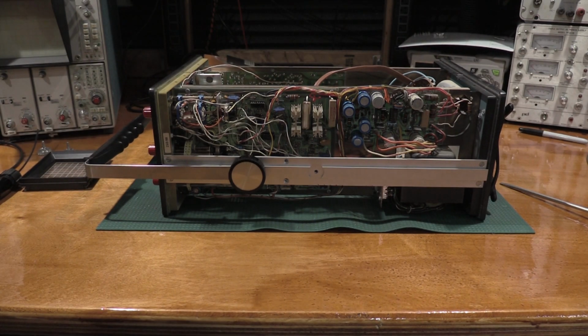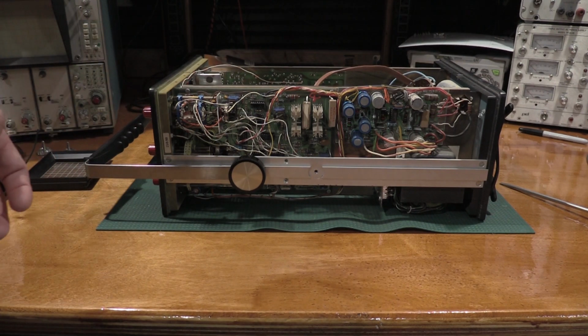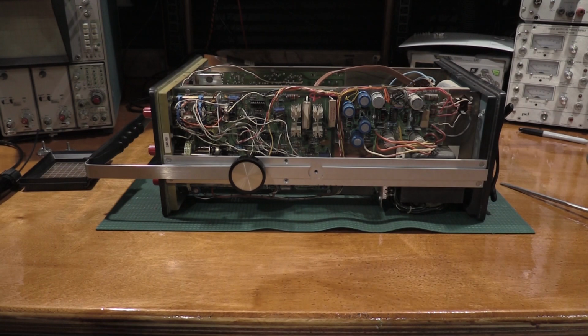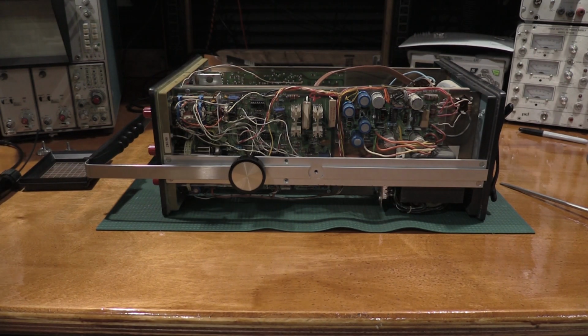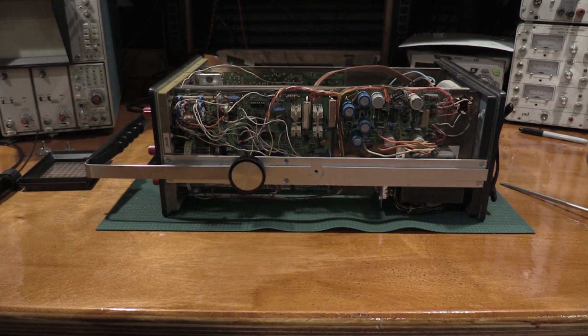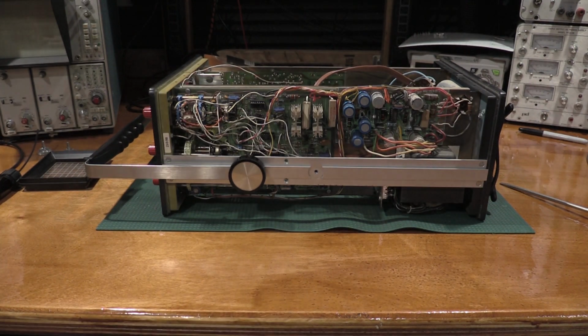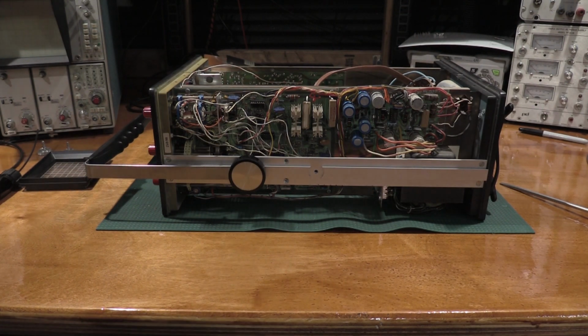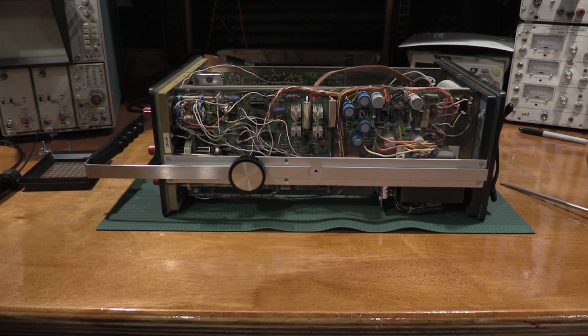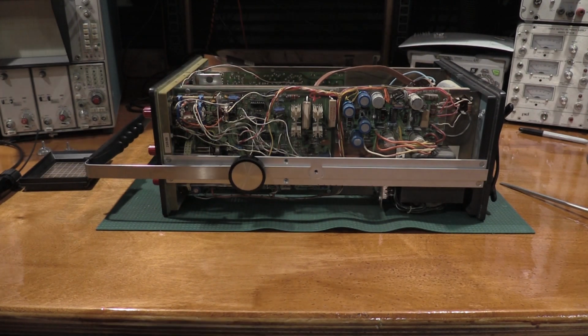So use extreme care when handling CRTs, especially these electrostatic CRTs. They do not have the shadow mask that a TV does. The front face of an old style television is actually pretty durable because it's got a whole bunch of layers. The shadow mask is up there, which is a steel grate, and a few other things. And the glass is super thick. On these CRTs, that's not necessarily the case. That's why all of the Tek scopes that I have actually have implosion shields, just in case the tube decides to pop while it's under power in the device. I haven't heard of that ever happening, but Tek was worried enough about it to put an implosion shield between the user and the tube. So especially when handling CRTs and large vacuum tubes, especially high vacuum tubes, use extreme care and be very careful.